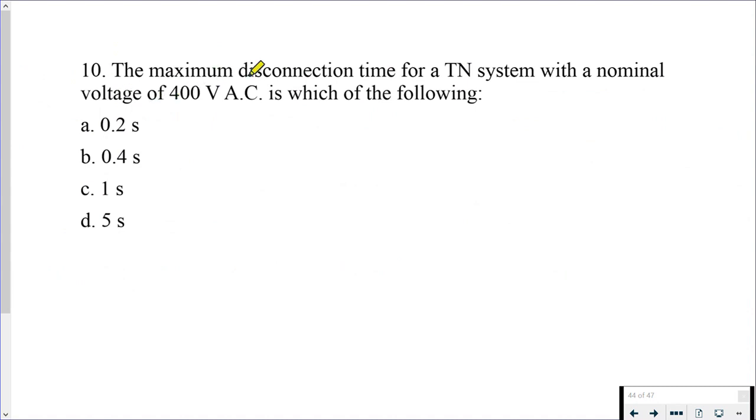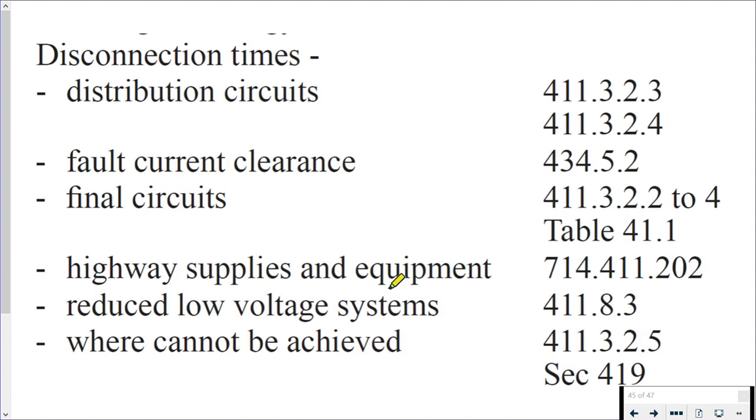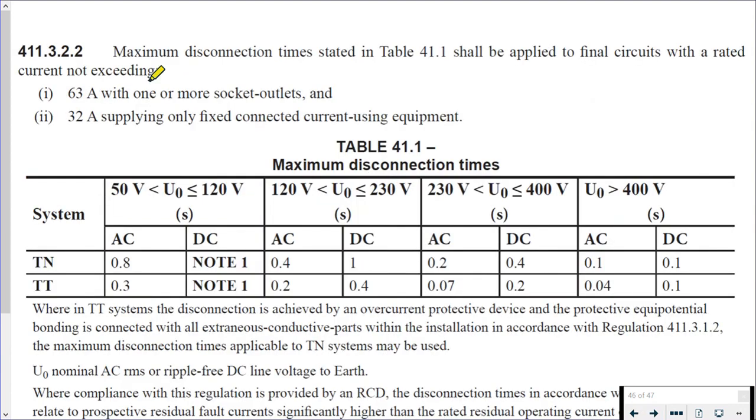Question 10: the maximum disconnection time for a TN system with a nominal voltage of 400 volts AC is which of the following? So it's a disconnection time, we're looking at disconnection times max, and we're also going to be looking at that 400 volts. If we have a look at disconnection times, we have distribution circuits, fault clearance, and final circuits. Now the fact that it didn't mention distribution circuits leads me to believe that we are looking at final circuits. So final circuits, 411.3.2.2 and table 41.1. If we look at 411.3.2.2, that gives us the basic general circuits that we're dealing with, and then it takes us to table 41.1. We've got that less than or equal to 400 volts. So for a TN system, for a 400 volt TN system, it's 0.2 of a second.